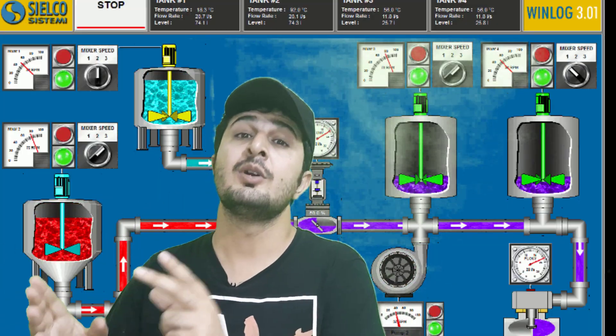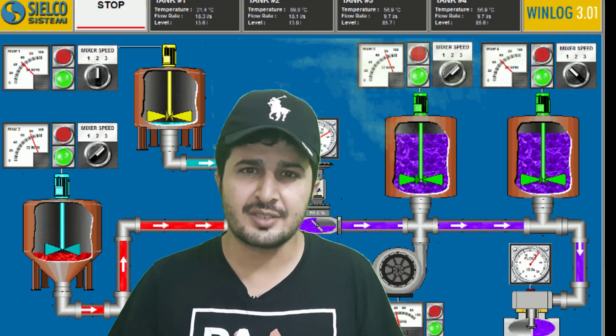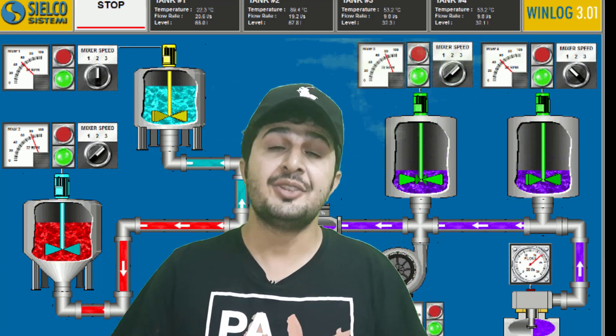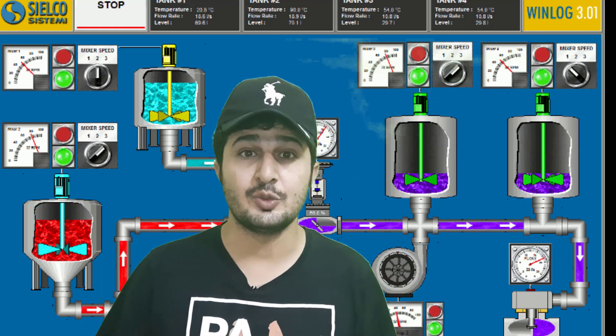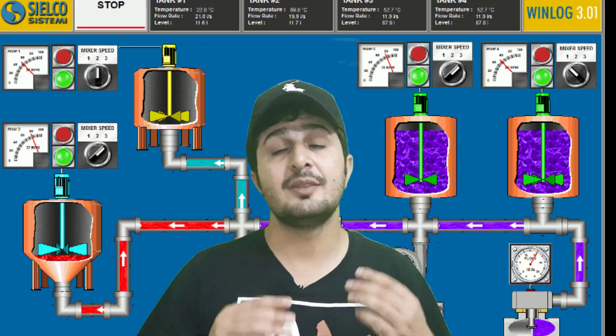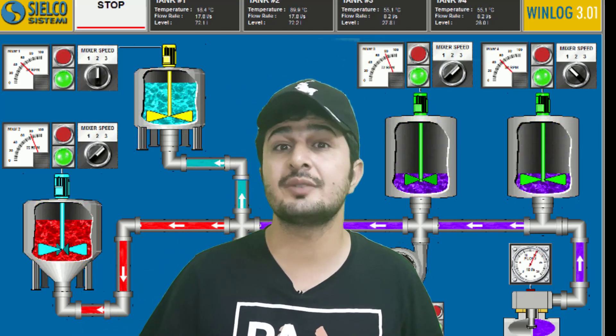DCS systems are redundant — each area has two controllers instead of one, and each unit is managed and controlled by a separate set of two controllers. If the system is redundant, operations run smoothly with less chance of downtime. However, this redundancy feature makes the cost of a DCS system comparatively very high compared to SCADA. SCADA can be implemented at lower cost, and redundancy is not a mandatory requirement in most SCADA projects.